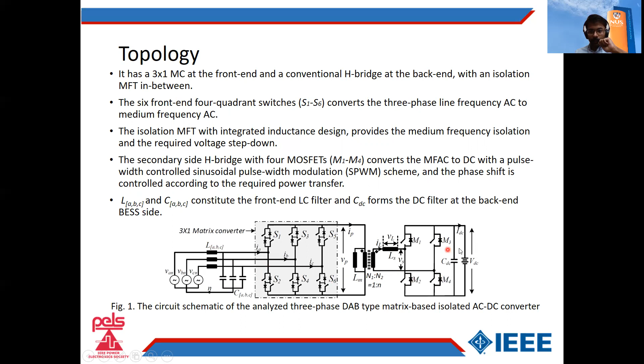The secondary side H bridge is a conventional one which converts the medium frequency AC to DC and also ensures that a controlled sinusoidal pulse width modulation scheme is implemented. And there is also an inter-bridge phase shift which can be controlled between them to facilitate the required power transfer. Now L_ABC and the C_ABC are the AC side LC filter and the C_DC constitutes the DC side filter.